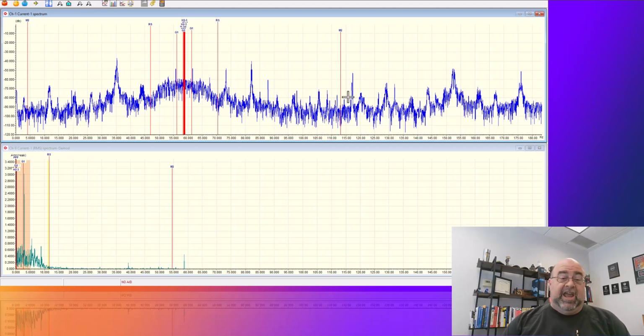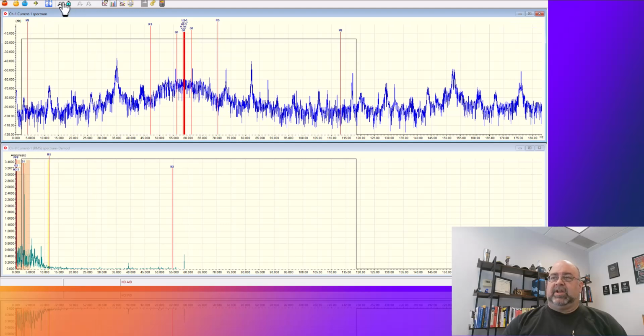Because they're not capable of doing it or understand the technology, they'll challenge those who actually do the work. So I'm taking data off the back of an SEL in this case. The result of taking data off the back of a medium voltage piece of equipment is that you sometimes will get a phase shift. It depends on the accuracy of the CT. They've got low quality CTs in here, and there's a lot of things about some applications that I'll comment on.